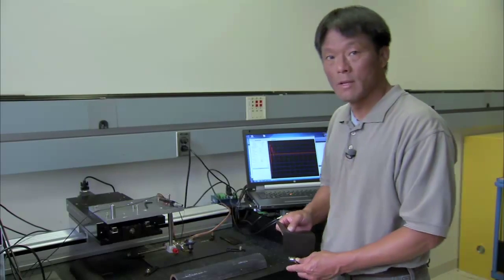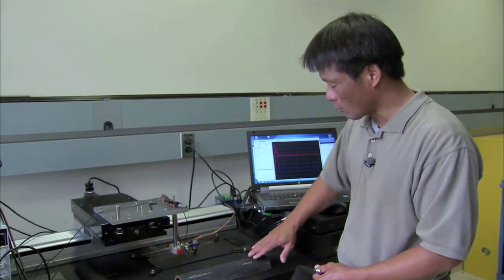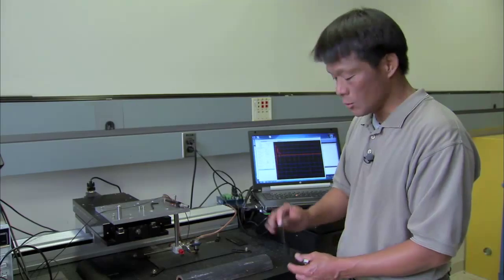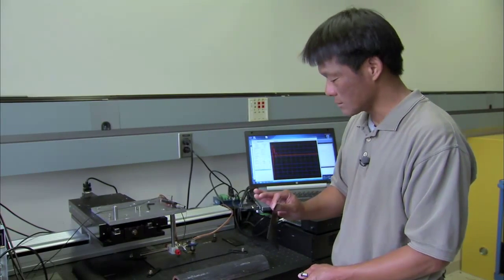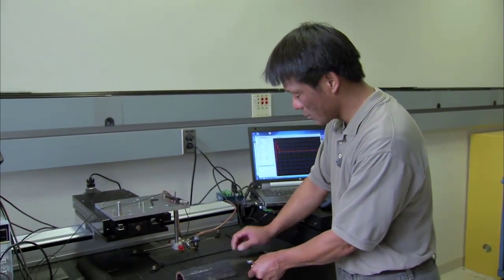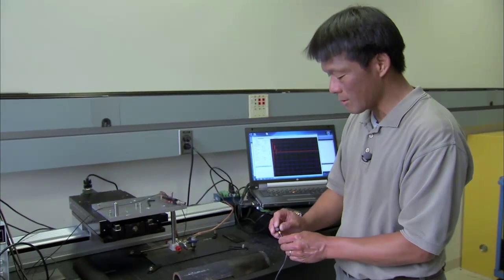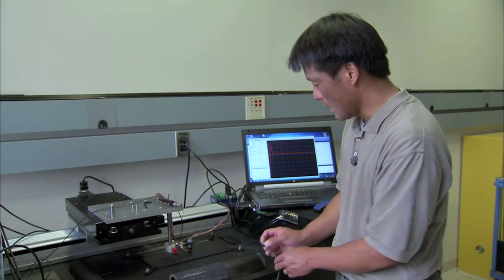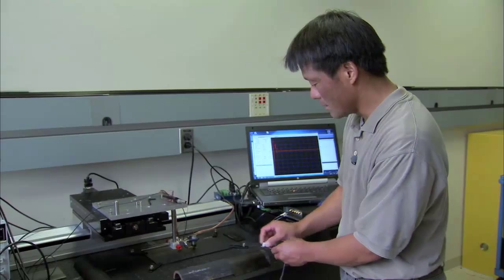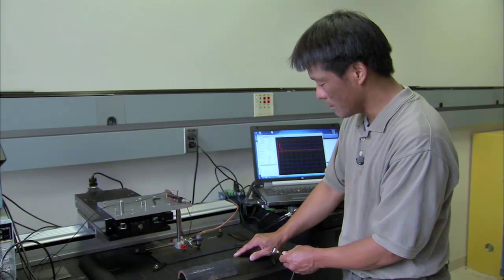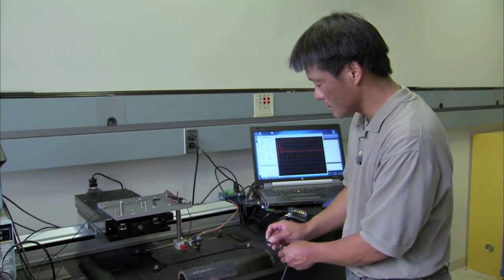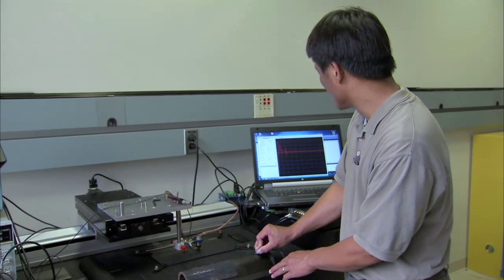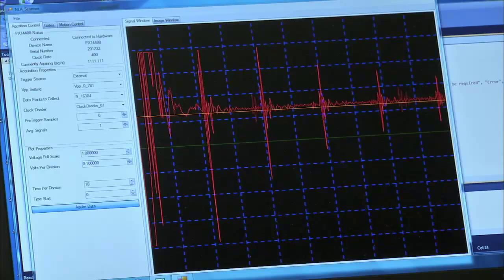One possible benefit of using the solid couplant membrane is if you have a rough surface that you have to inspect, you can go to thicker membranes. So you can lay that over the sample. You can either lay it over the sample or have it on the transducer, and then the thickness of the membrane will account for the surface roughness, so you can still do your inspection over an area that's rough.